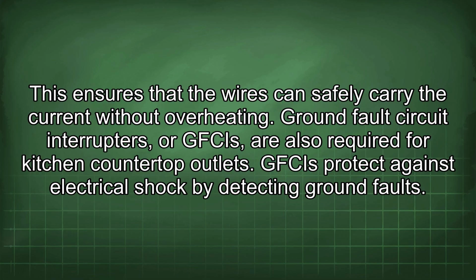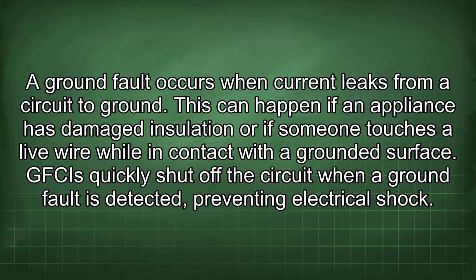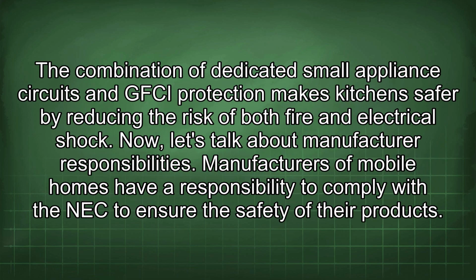GFCIs protect against electrical shock by detecting ground faults. A ground fault occurs when current leaks from a circuit to ground. This can happen if an appliance has damaged insulation or if someone touches a live wire while in contact with a grounded surface. GFCIs quickly shut off the circuit when a ground fault is detected, preventing electrical shock. The combination of dedicated small appliance circuits and GFCI protection makes kitchens safer by reducing the risk of both fire and electrical shock. Now, let's talk about manufacturer responsibilities.